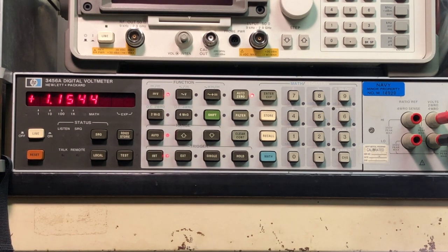So the next thing that I need to do is position things to take a measurement on the internal ovenized crystal oscillator, but the instrument needs to run for 24 hours before I do that. So I'll let it sit here, and then I'll get things connected, and then we'll take the measurement and set that internal oscillator, because I do know that it's off just a little bit, so we want to bring that into specification. We want to bring it right to 10 megahertz.